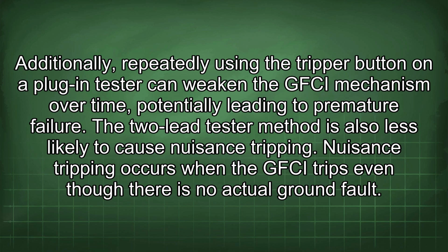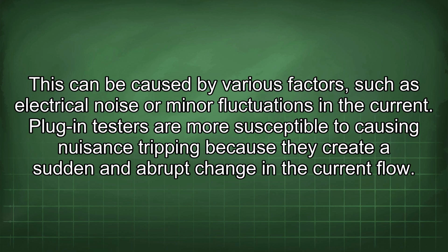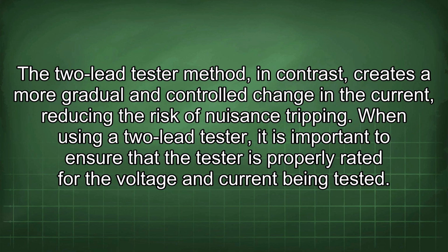Nuisance tripping occurs when the GFCI trips even though there is no actual ground fault. This can be caused by various factors, such as electrical noise or minor fluctuations in the current. Plug-in testers are more susceptible to causing nuisance tripping because they create a sudden and abrupt change in the current flow. The 2-lead tester method, in contrast, creates a more gradual and controlled change in the current, reducing the risk of nuisance tripping.